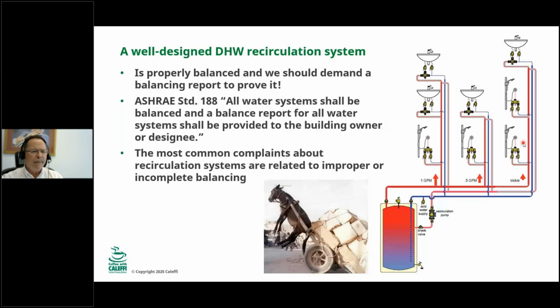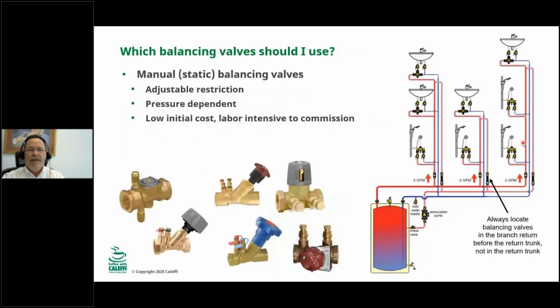Let's talk about balancing valves for a couple minutes. There are three types: manual, called also static balancing valves. These are all just an adjustable restriction in the line. That's all it is. They don't have any moving parts. They're pressure dependent. That means that the flow through them will change as the pressure changes. Once you set them, they're just a restriction in the line. Okay, they're kind of the traditional valve that's been around forever.